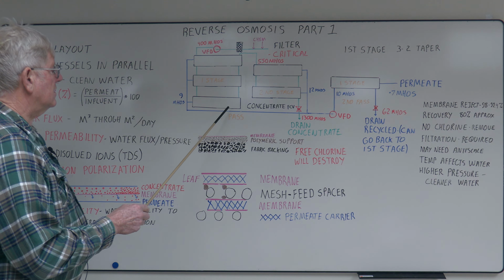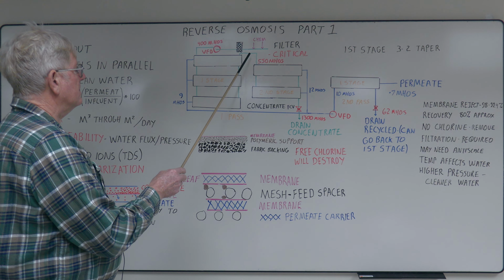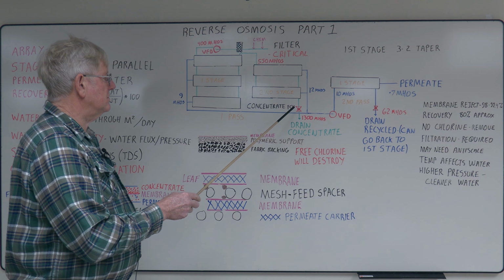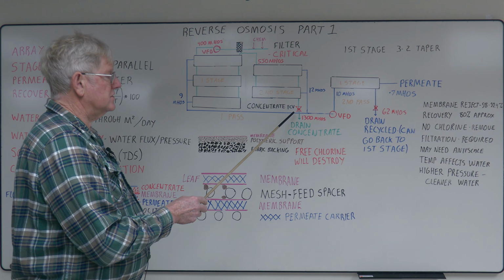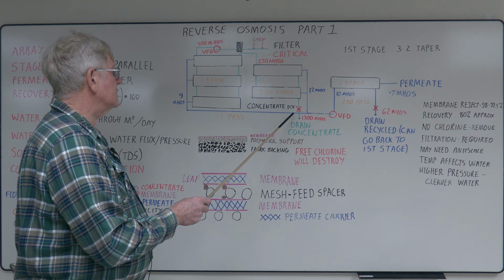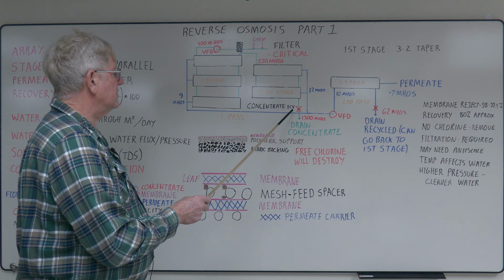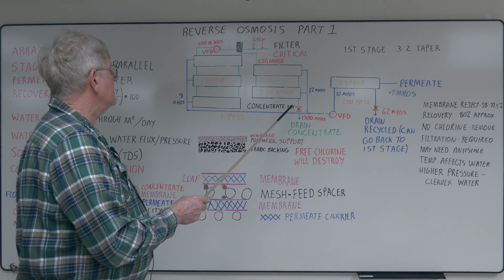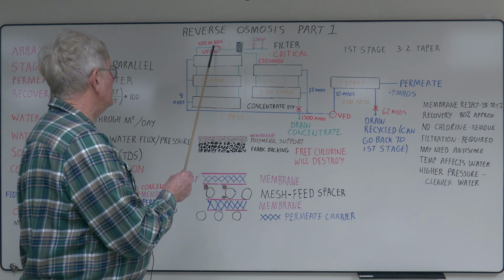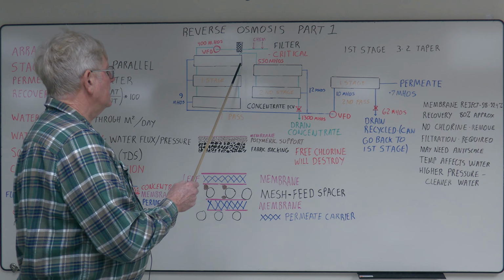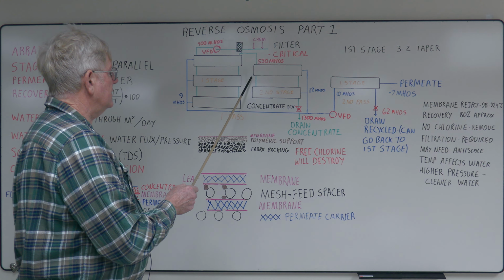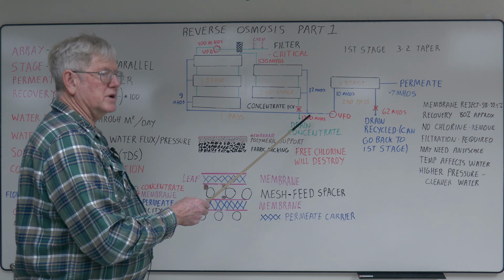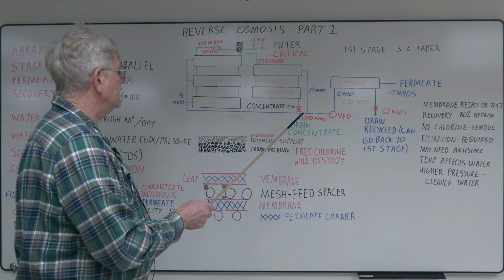You take the concentrate from the first stage and you feed it to the second stage. And the key valve here is your concentrate flow control valve. This is never adjusted. Once you set the unit up, this controls your recovery rate. And it can also tell you how your unit's running. Say you have 400 micromhos water coming in. It could be 550 micromhos feeding your second stage, and coming out can be 1300. Probably getting pretty close to forming scale here.